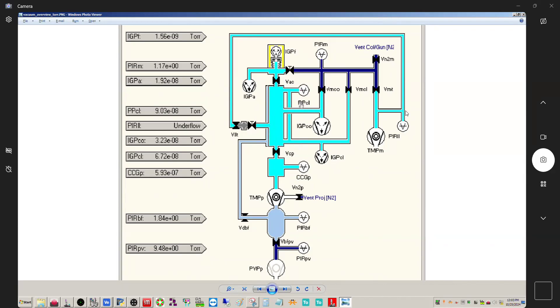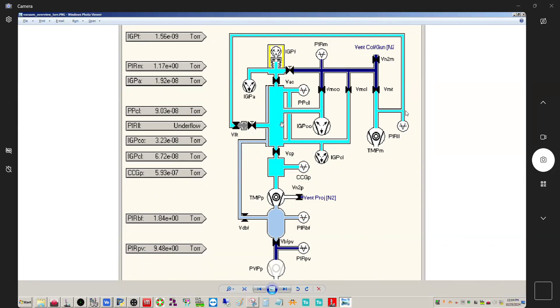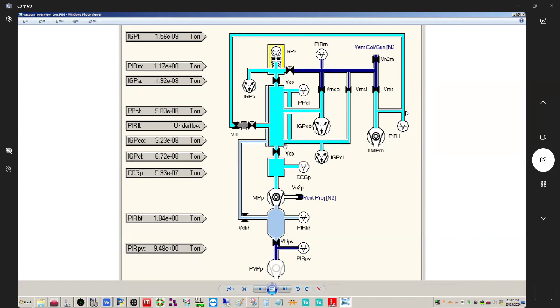So this PPCL, this is the column liner. The IGPCO, this is column octagon. So as far as liner and octagon, if you go back here, you can see in your vacuum panel, you have reading for liner and octagon. So that's what this means, the L and the O here. So the IGPCO, this pumps on the specimen area, the IGPCL, this is column liner, this pumps far down lower in the column, I think in the selected area aperture vicinity. So this is higher up or lower down the column, so to speak. Then you have another valve that isolates the column from the projection system. So when you open the column valves, you're opening literally these two valves. So right now column valves are closed. So you have VCP for valve between column and projection.